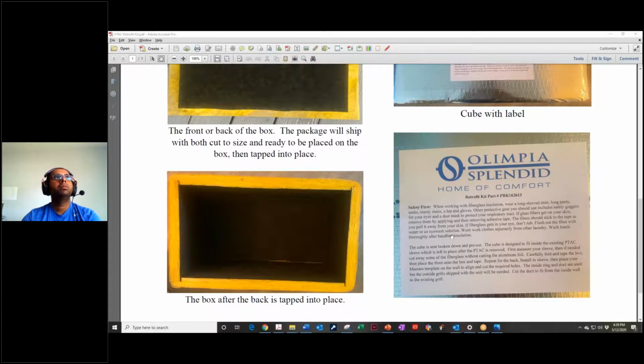So one of the applications I have in Miami that we just had installed with these kits is the PTAC, the shell, actually extends into the room about 3 inches. So that's not a problem. We just cut that 3 inches off right at the wall. And then the unit mounts on the wall like normal, and the hole is well insulated and sound attenuated. So I think this is going to be good. We're going to have these on the market for you folks to purchase in one of two sizes, because typically there's the 32 inch PTAC and the 42 inch PTAC, but we will have kits for both of those for retrofit.